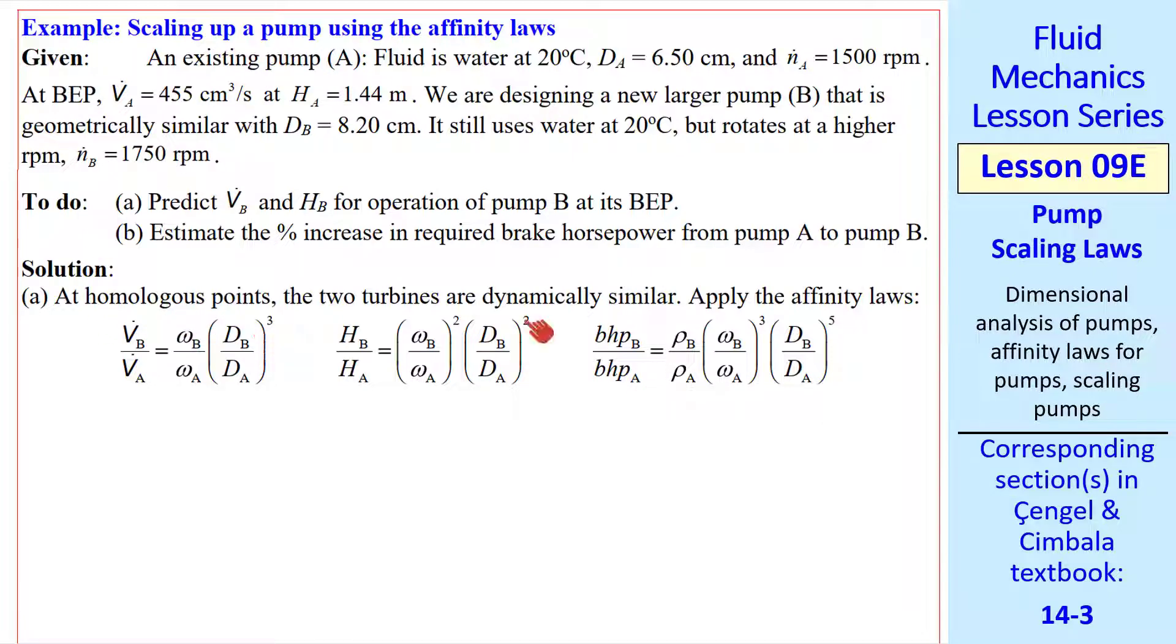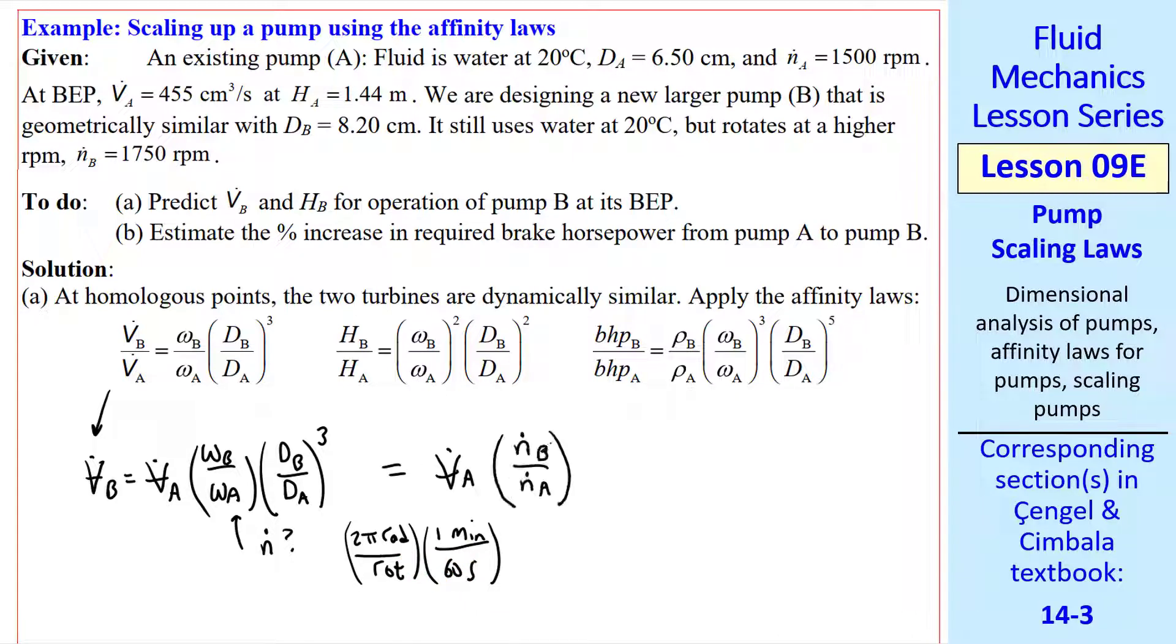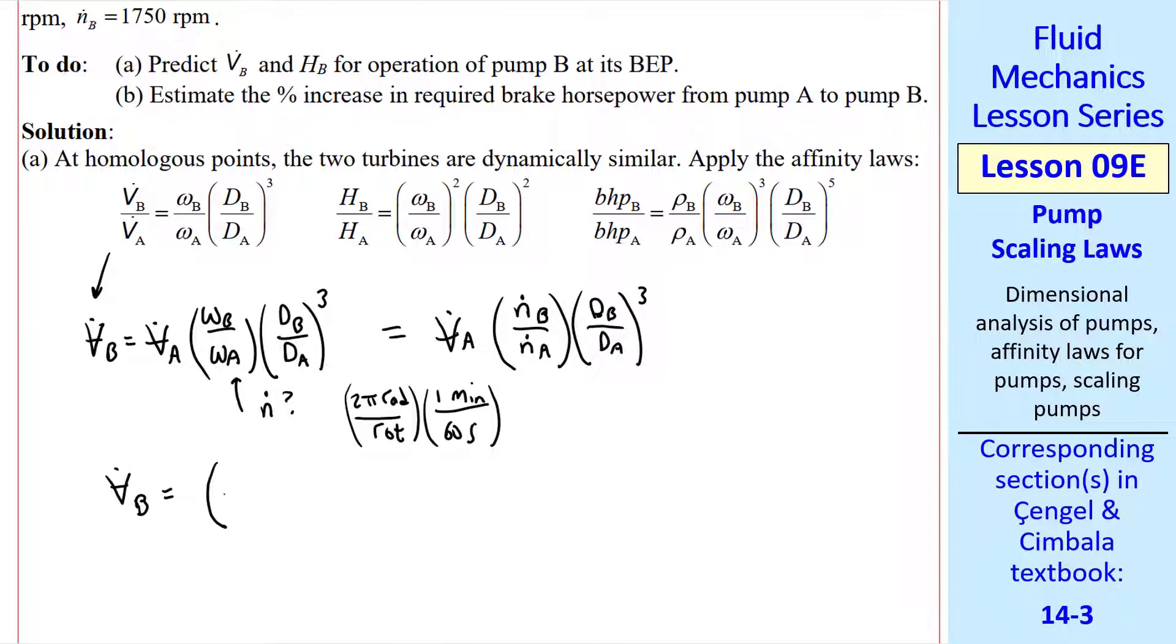So V dot B is V dot A times the ratio of omegas times the ratio of diameters cubed. We want to use N dot, so we'd have to convert using two pi radians per rotation and one minute per 60 seconds. But since we'd be applying these unity conversion ratios on both the numerator and denominator, the two pi's, the 60's, and these units all cancel out. So we can write this as V dot A, N dot B over N dot A, DB over DA cubed. This is the case only if you do the same thing on the numerator and denominator, so be careful. Using the given values, we calculate V dot B as V dot A times the ratio of RPMs times the ratio of diameters cubed, and we get this value.